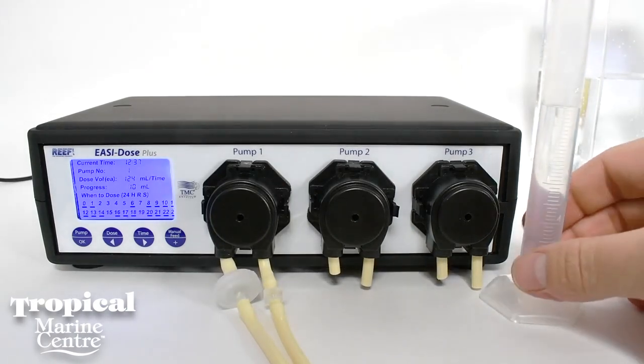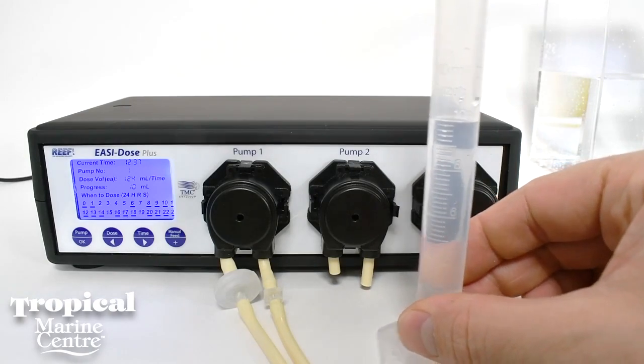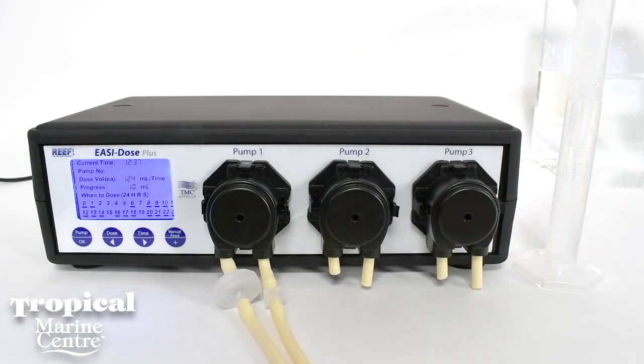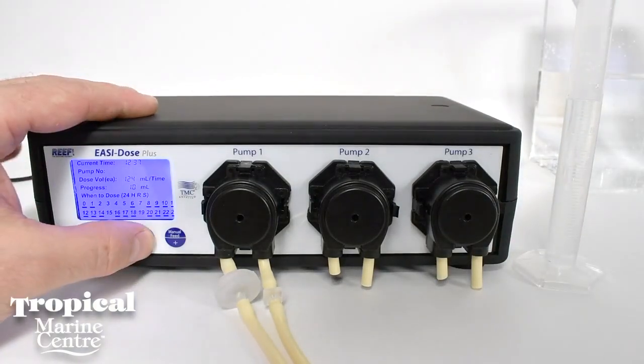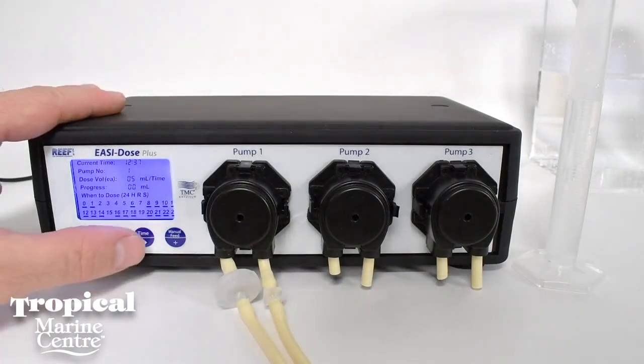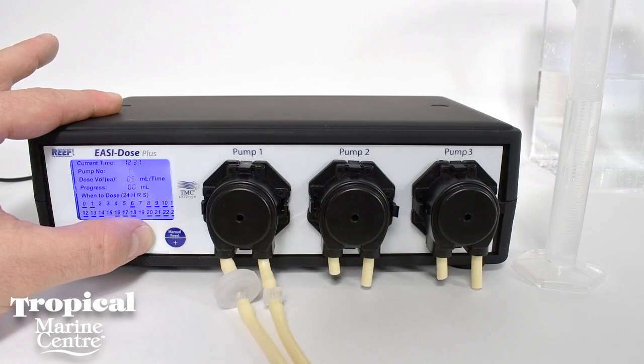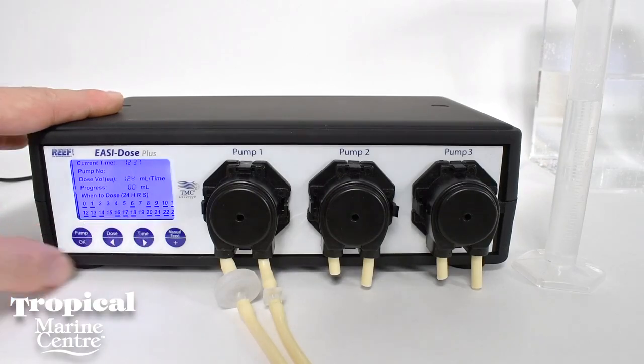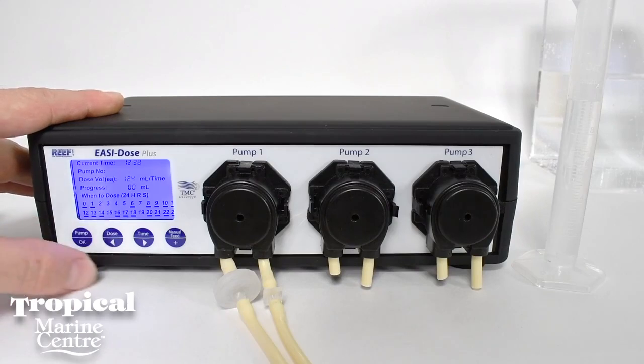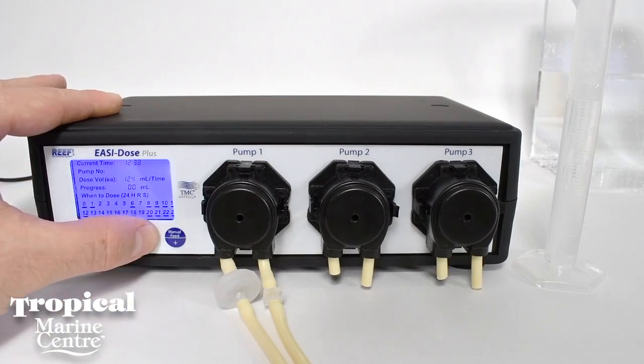Always check the measuring cylinder on a level surface. You can see we now have exactly 10ml. We want to save this calibration. All we do is press and hold the time right button until the clock starts flashing again. You'll need to do this process for all of the pump heads. To select the pump, you must do it whilst in calibration mode, with the pump number flashing.